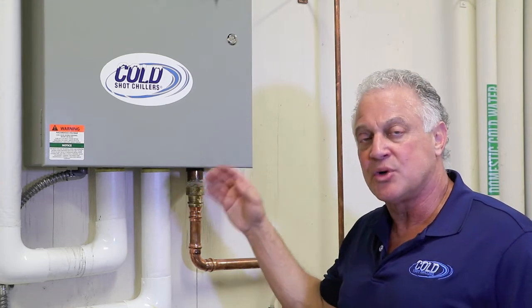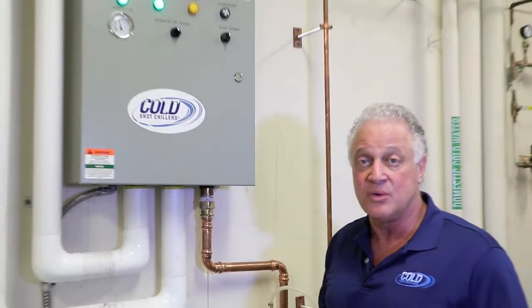Okay, this system is equipped with the highly recommended automatic city switchover. In the event of a mechanical failure, this box will switch the cooling medium from the chiller loop to the city water supply, so the linear accelerator does receive the necessary cooling needed.